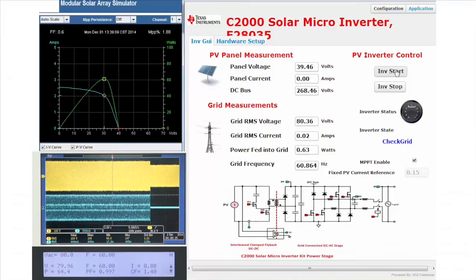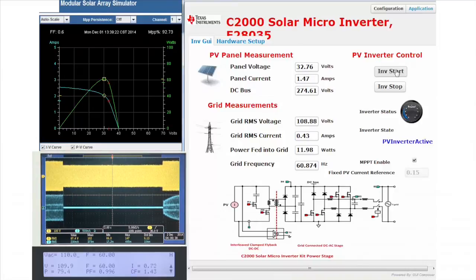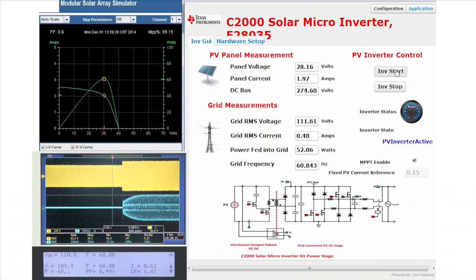Once again, when the voltage recovers or the sag is over, the inverter starts up again and tracks back to the maximum power point. Similar behavior can be observed in case of complete grid loss and panel under voltage.